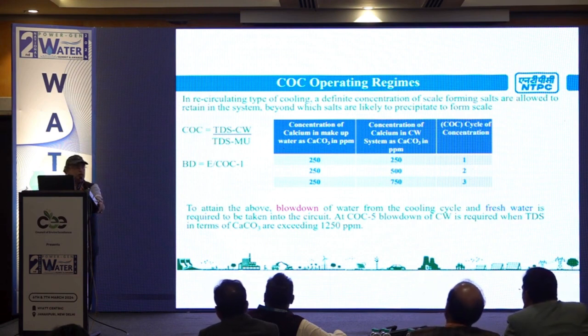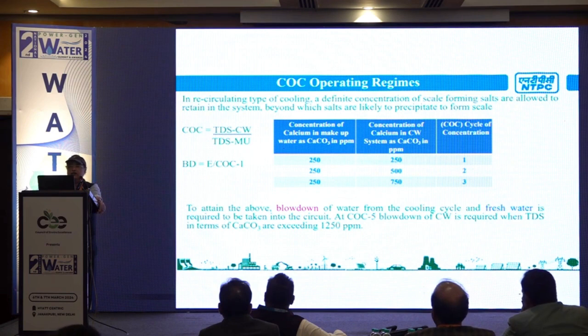As the COC increases, our blowdown extent decreases. It's a known fact. At Jhajjar we have around 250 TDS. So at 5 or 6 COC we are managing up to 1250 to 1500 TDS.